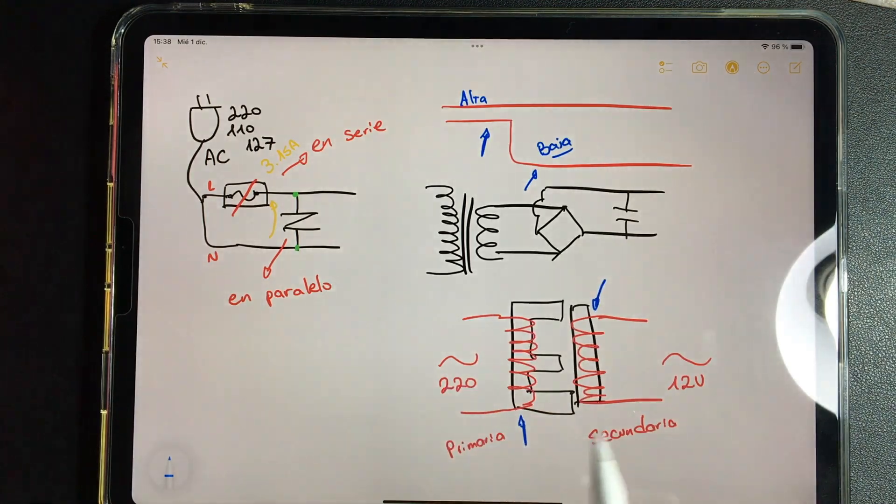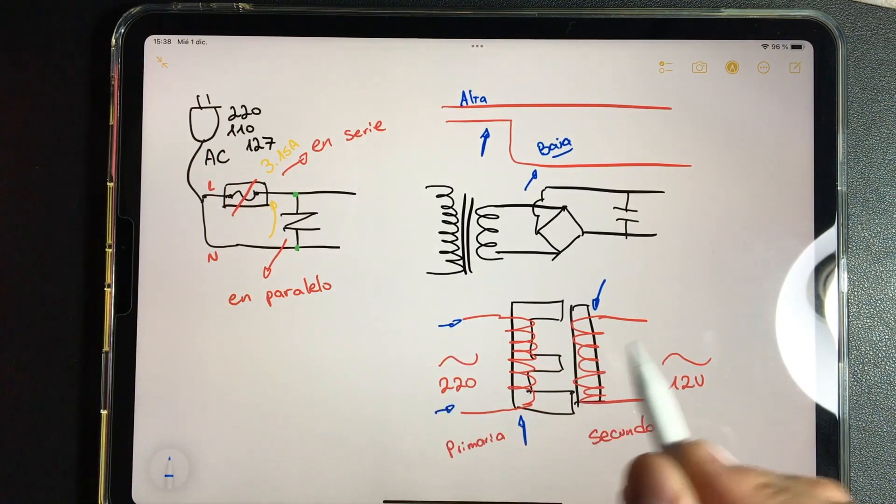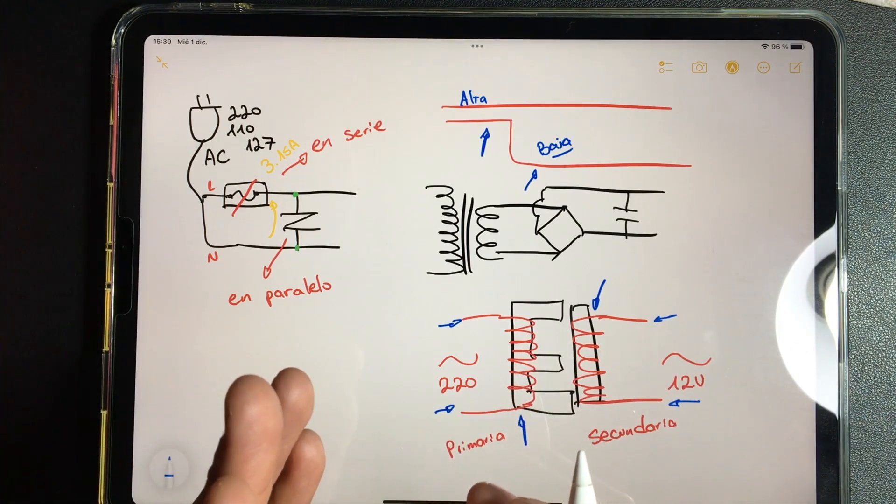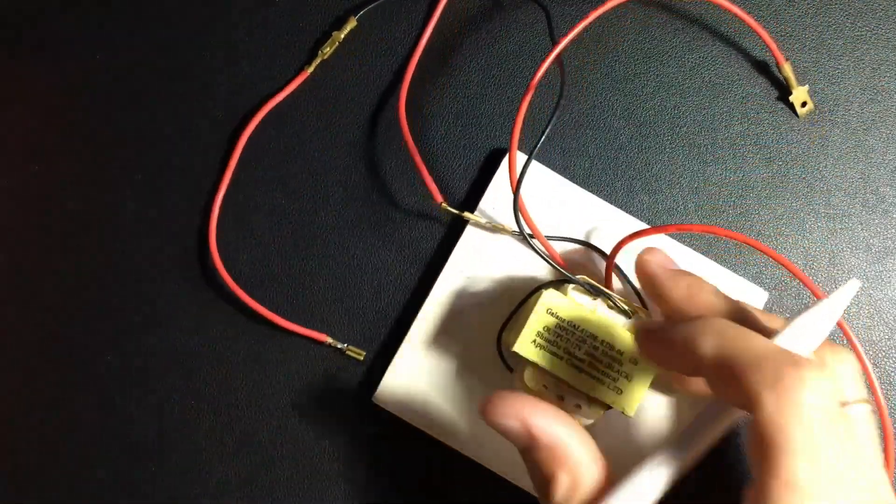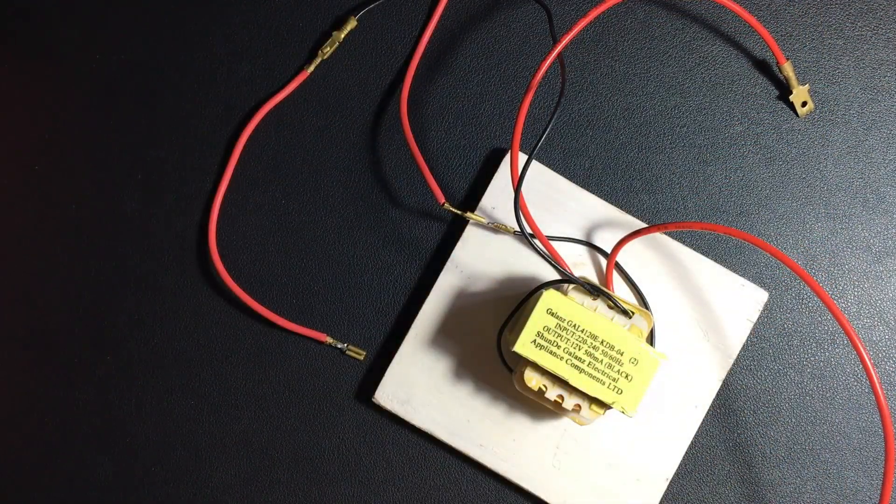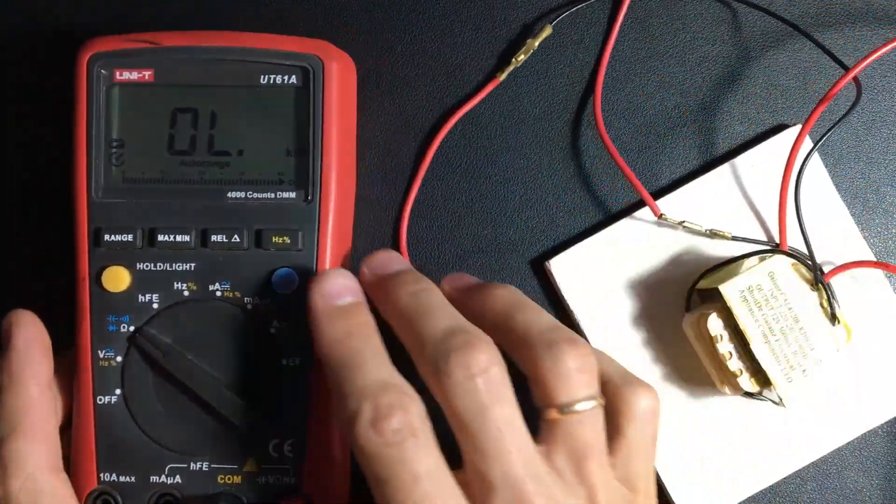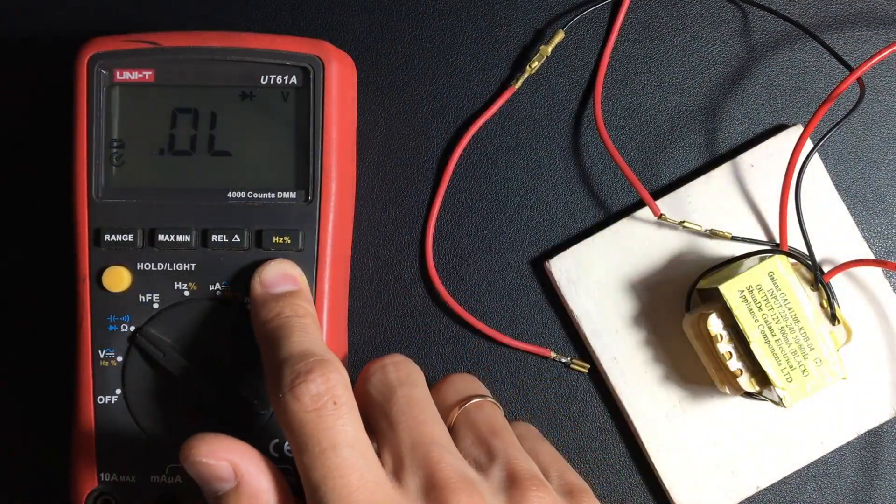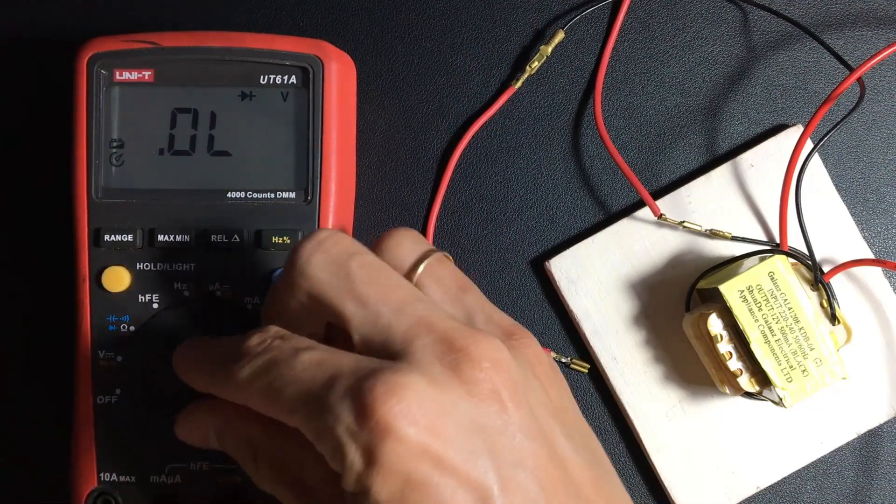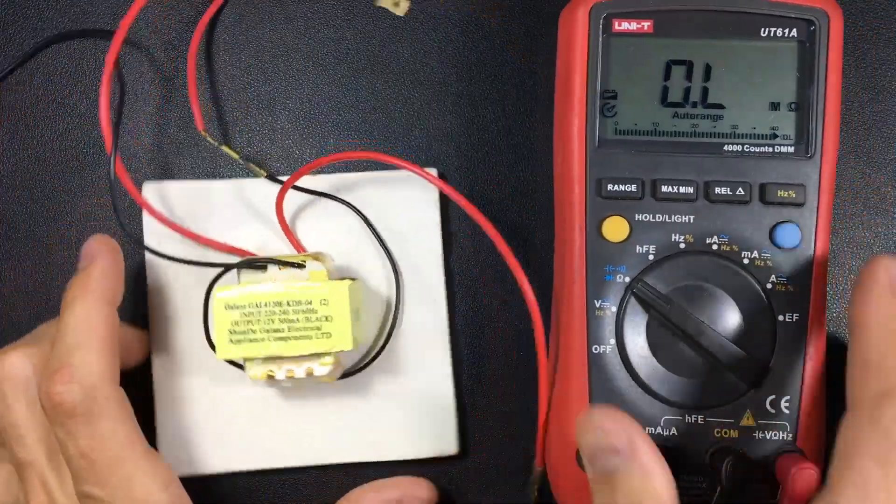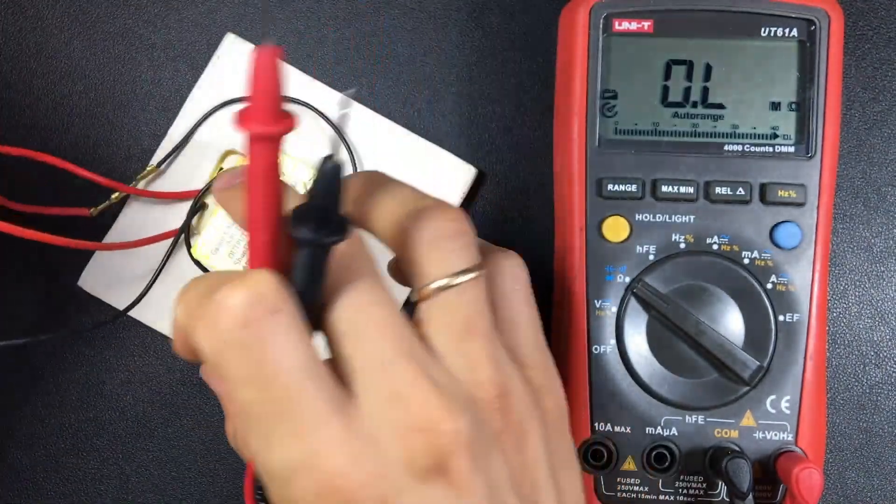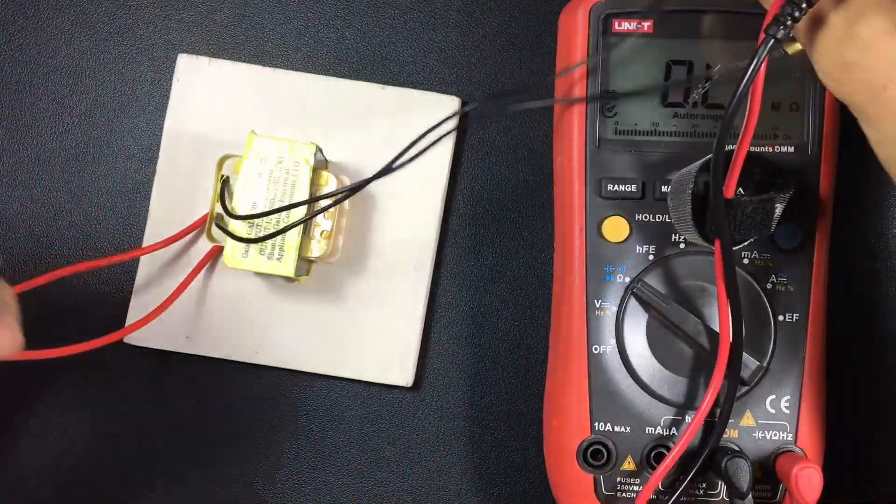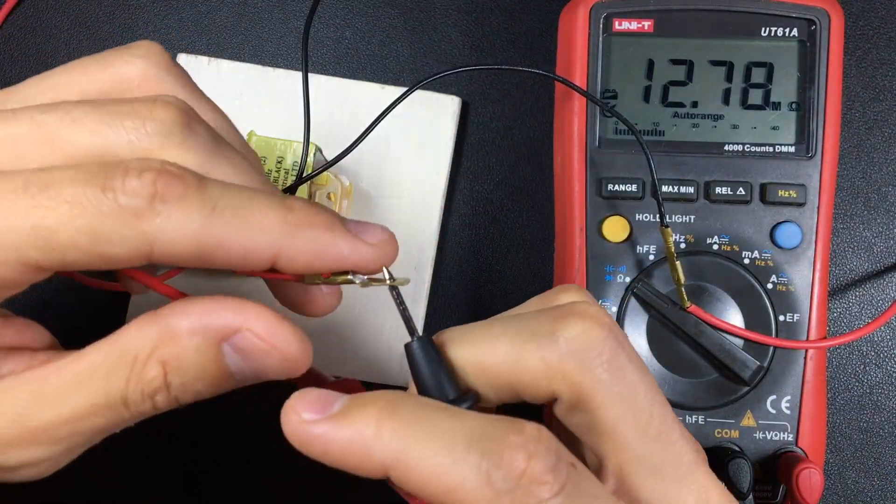This is important to understand because now I am going to teach you how to check if it is in good or bad condition, but without voltage. We are going to do it a safer way. We are going to corroborate it with resistance. Let's grab our transformer and set the multimeter to resistance. What we are going to do now is control the primary side. The primary side is generally the thickest wires and the secondary side is the thinnest wires. We will control the primary side and look what we find.